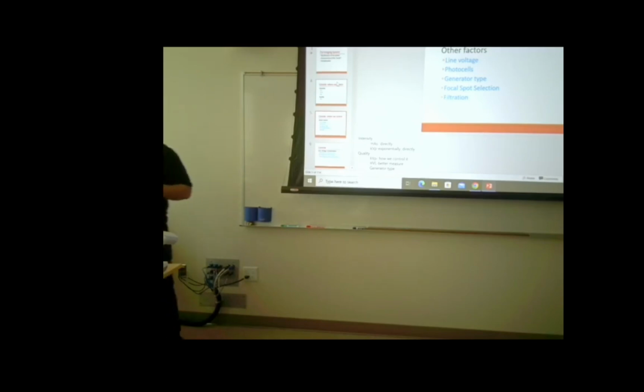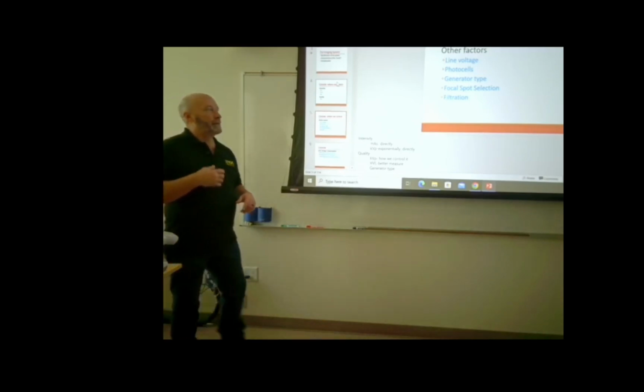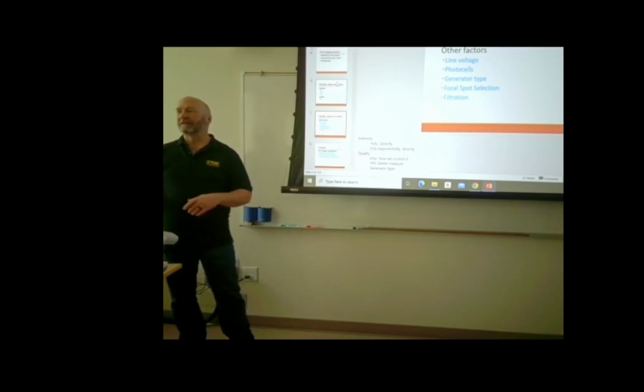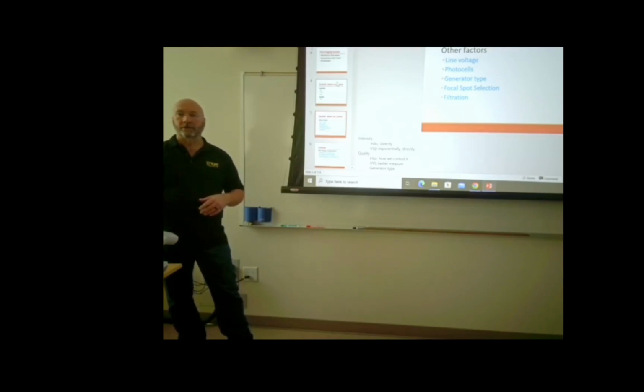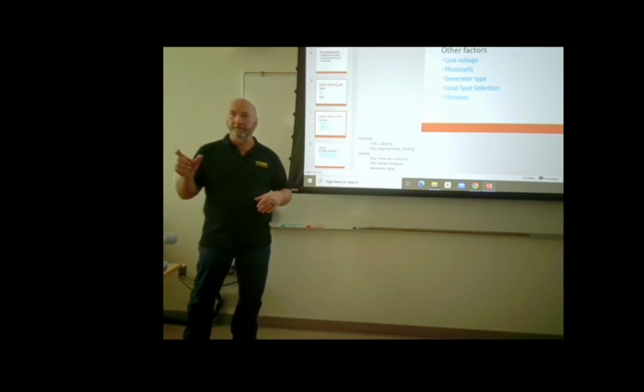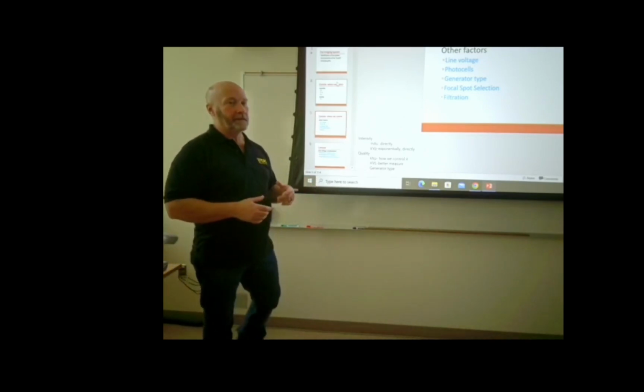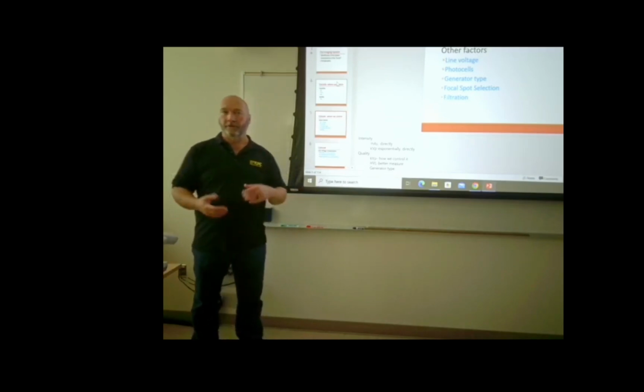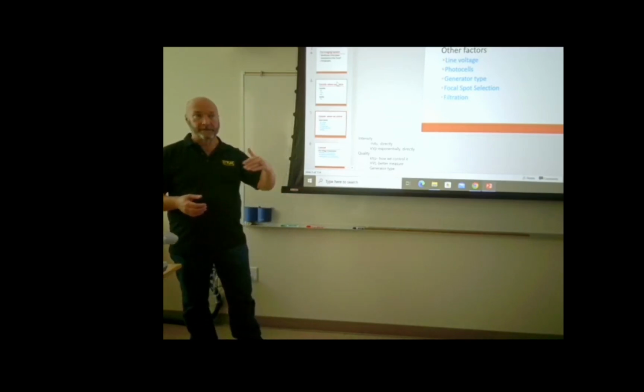All right, so other things that we control would be our line voltage compensation. We really don't control that unless you're working off of an old single-phase system. You're just not going to see that. It's going to be built into the system. You can do a Google search, and you can find a control panel where it actually has line voltage compensation on the control panel. But in any three-phase or high-frequency room, you're just not going to see that. It's built into the system.